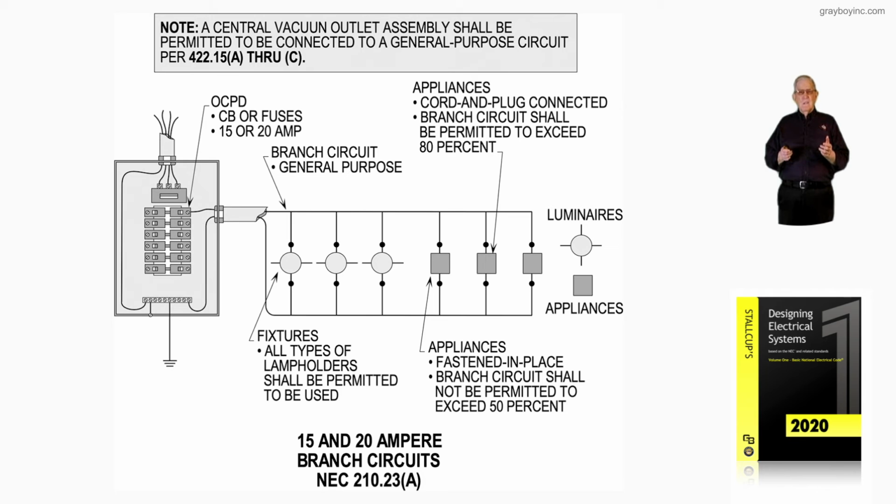And to really get a feel for this, like I previously mentioned to you, you'd have to use 210.21, 210.22, 23, 24, but just go to Table 210.24 and everything is listed there for you on all circuits where you could have dual and combination loading, up to a 50 amp overcurrent device.